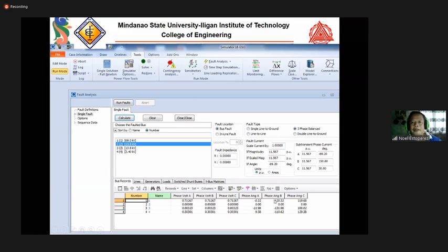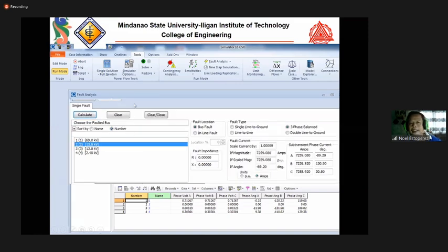Okay, and then we have the 3-phase fault at the 13.8 kV side. Same procedure, if we calculate that, we get 7,200, which is also very similar to our computation of about 7,300.